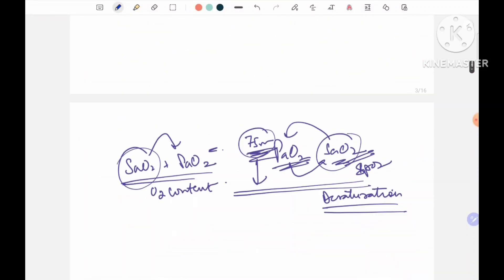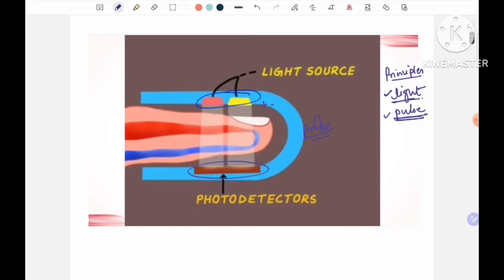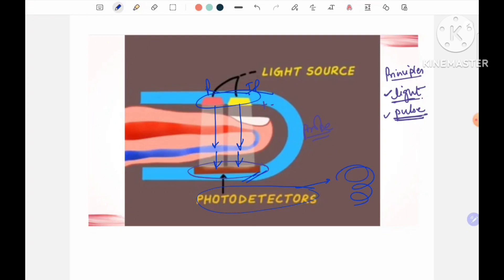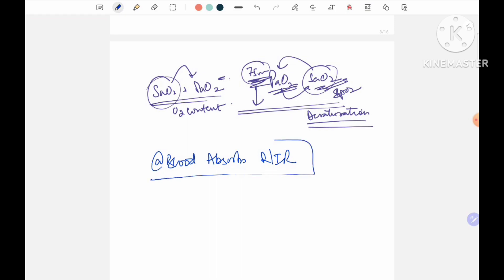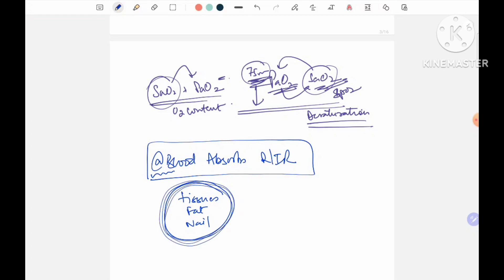The light source in the probe contains two lights - red and infrared. When these two are thrown on the tissue, whatever is transmitted is picked up by the photodetector, and that data is sent to the microprocessor for further analysis and comparison with the pre-fed data. But when we are putting a patient's finger in the probe, how does the pulse oximeter know it is really arterial blood? There are other things present too - tissues, fat, a nail. How does the photodetector know to subtract the intensity loss from these other tissues?